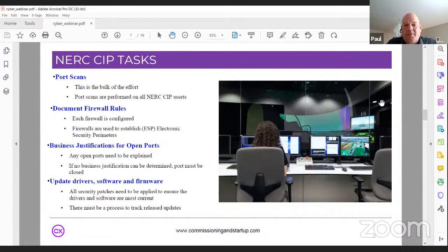Throughout commissioning and even after systems are in service, there are constantly updated drivers, software, and firmware being issued. At in-service date, all security patches need to be applied to ensure the system is up to date and addressing any known vulnerabilities. All those software patches need to be reviewed and updated at in-service date, and even after, any new patches or firmware updates need to be monitored and applied to the system in a timely manner.